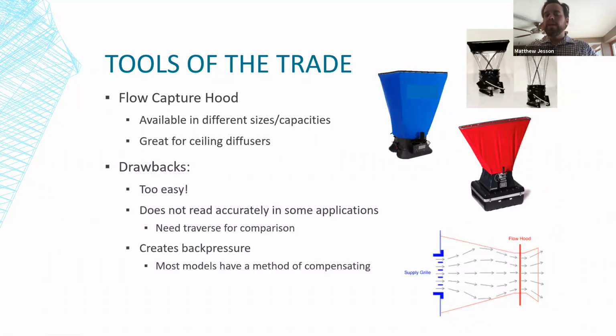So part of what it does is it actually creates back pressure. You put that up against a diffuser and it'll actually decrease the airflow coming out of it to some degree. So that can skew how it reads. And most of the models that are out there have some sort of method for what's called back pressure compensation to try to calculate what would the flow be if I didn't have the hood up against it. So that can be an automatic function of the meter, or it can be a manual function.